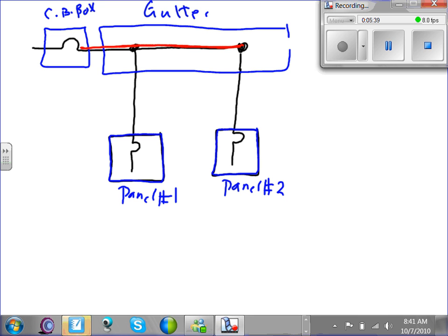This one here? No. No, why? Because it received its power. It has an overcurrent device at the point that it received its power. It's not a tap. So the tap is when you have a conductor and that conductor does not have a circuit breaker located at the point of receiving the power. Okay? Let's take an example. So that's why it's a tap.